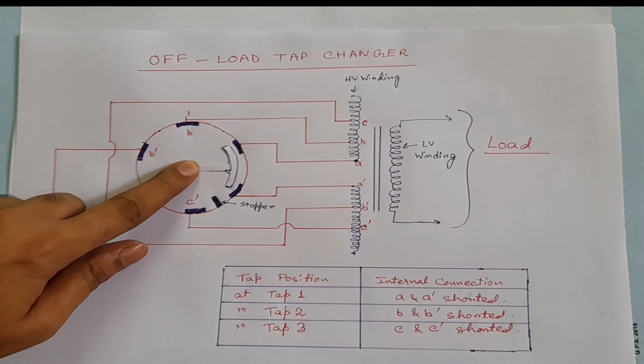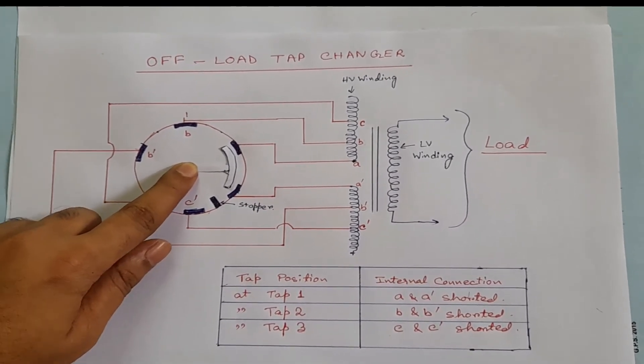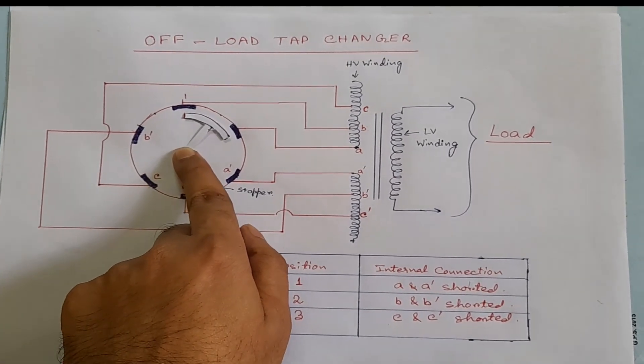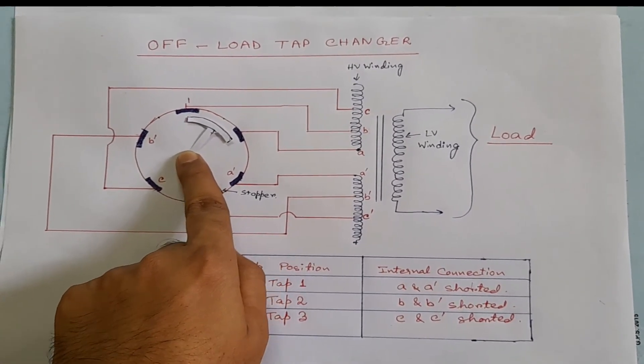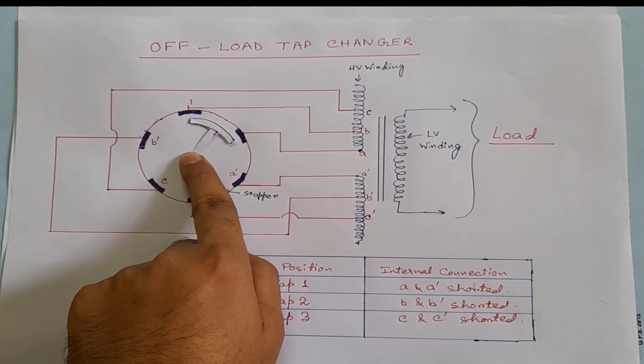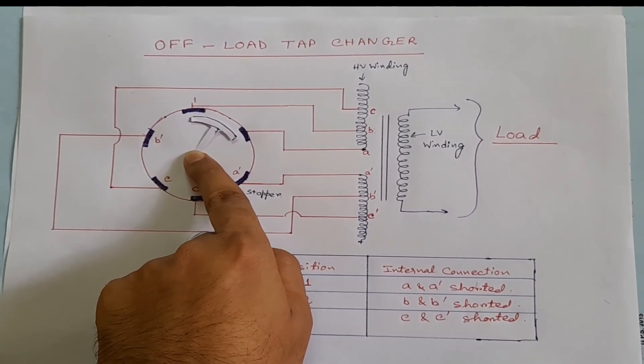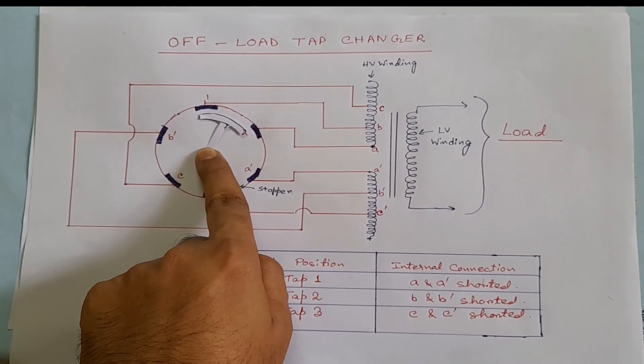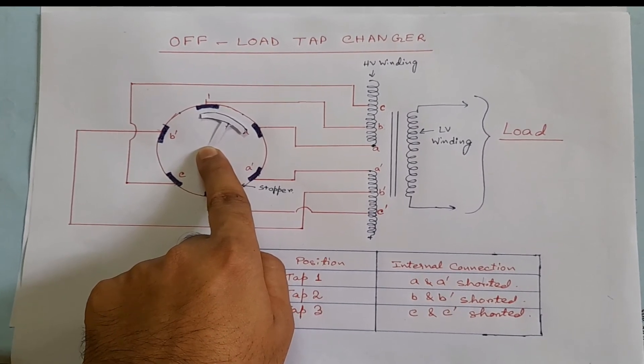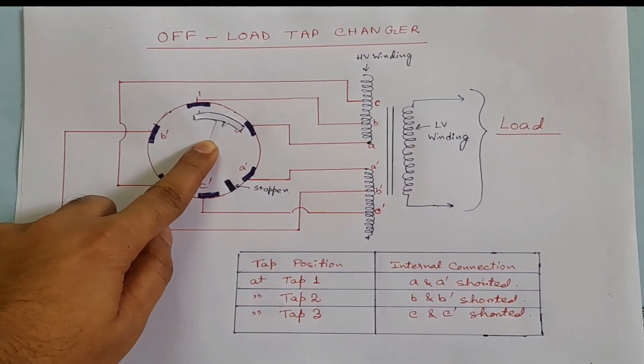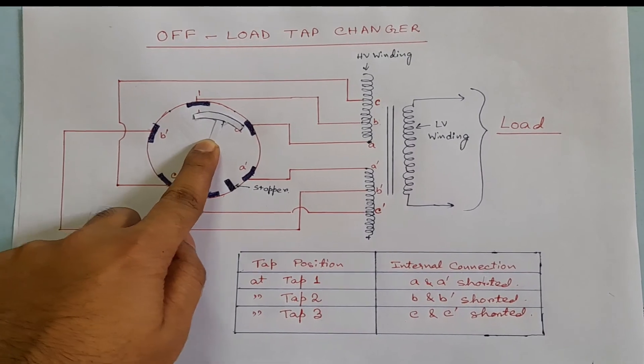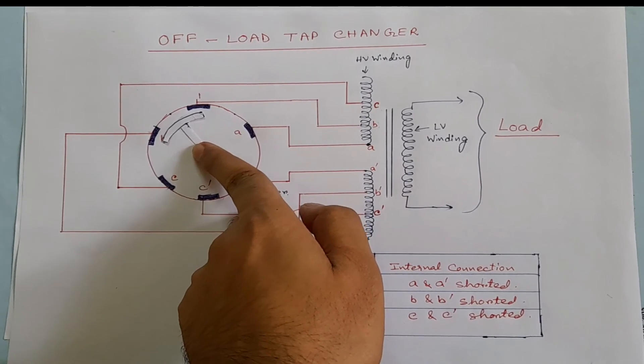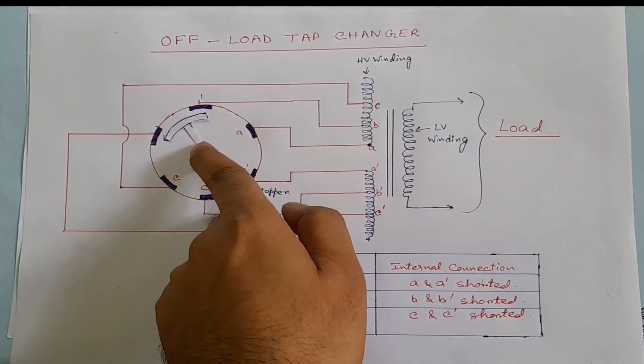Suppose we want to change tap from one to two position. For this, the shaft will start rotating, and at this position, notice that there is no continuity between the upper and lower side of the HV winding. So there will be a momentary disconnection. If this operation is done without switching off the load, then there will be a huge flashover in the off-load tap changer.